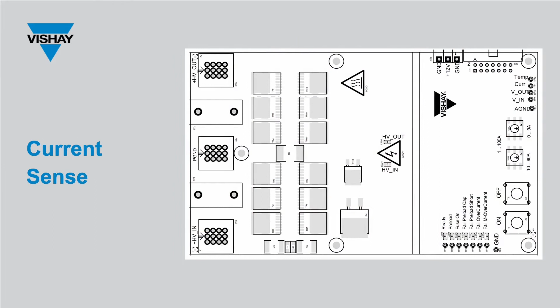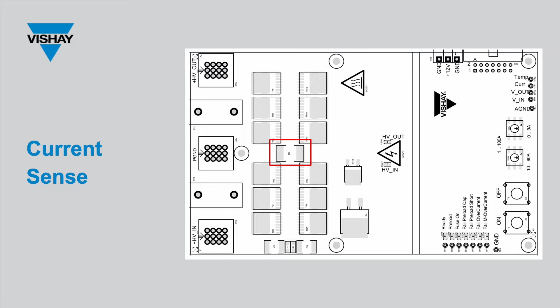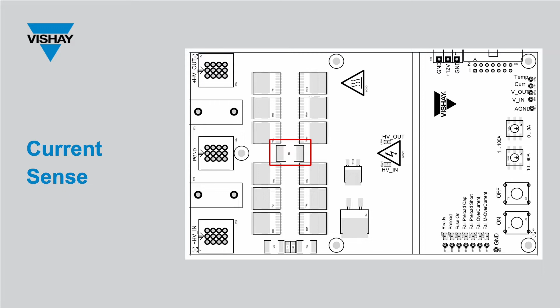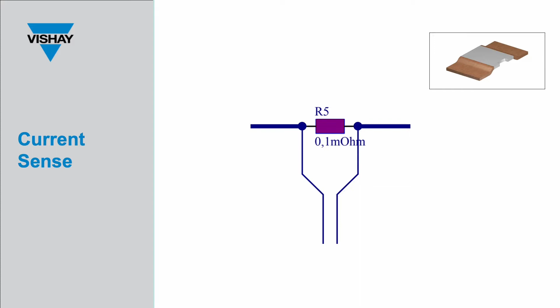Taking a look at the layout again, you can see the current shunt in relation to the two sets of power MOSFETs. Again, this symmetrical layout is used to minimize any stray inductance or capacitance and provide the best possible performance. In this design, a Vishay WSLP 3921 was selected with a 100 microohm value to minimize power dissipation and provide the best signal-to-noise ratio for the feedback circuit. A differential voltage measurement is taken across the current shunt and then fed into a current sense amplifier, which I'll discuss in more detail shortly.